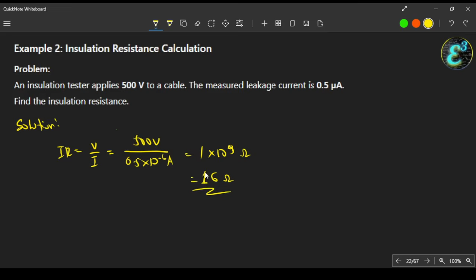Practical interpretation: high IR, which is good resistance, means high insulation resistance, good insulation. Low insulation resistance means insulation deterioration, meaning the insulation of the wire or system is slowly deteriorating due to moisture or chemical reaction or chemical corrosion. Wiring standards usually require that the insulation resistance be equal to or greater than 1 mega ohm. So that is the standard. If you are measuring an insulation resistance of any electrical circuit or system, it should be above or about 1 mega ohm. There are also specific current ratings of a circuit or plant circuit with their own required mega ohms, which we will discuss later, especially when we reach the Philippine Electrical Code.